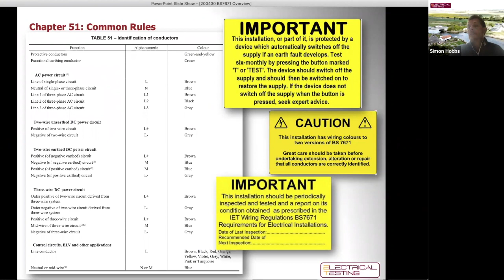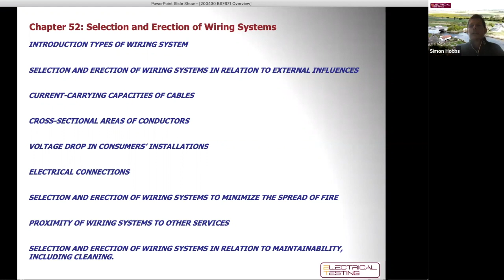Chapter 52 is a large chapter within part 5, and it is specifically about the wiring system. I've got one slide here on it, but it's about choosing what type of cable you're going to have, how big, what size the cross-sectional area of the cable is going to be, dealing with volt drop. It's looking at making sure that we choose the right cables so that if there's a fire, they won't propagate that fire. How we maintain the installation. It's also not just the cables, it's the installation system, the trunking, is it being buried in the ground, and so on and so forth. And this is all dealt with in chapter 52 so that we can design and select the right cables. We might be running steel wire armoured cables under the ground rather than a twin and earth or a small flex or something like that.